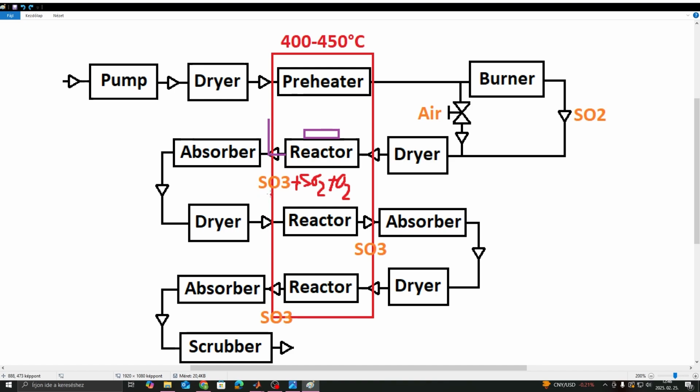And this is why, and also because the SO3, which is hot, and also the SO2, all these compounds are really corrosive at high temperatures. So after here, I would like to use Viton tubing and not insert the probe here, because it will corrode and degrade with not even that much use. So to avoid that, I will completely remove this temperature probe.